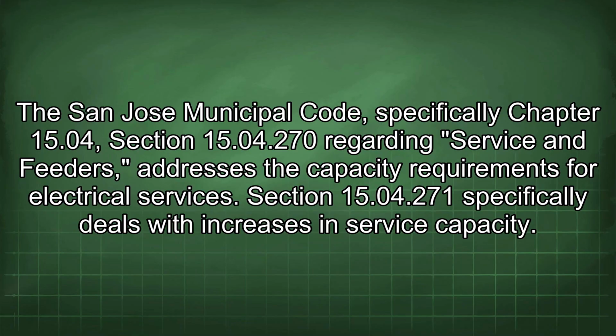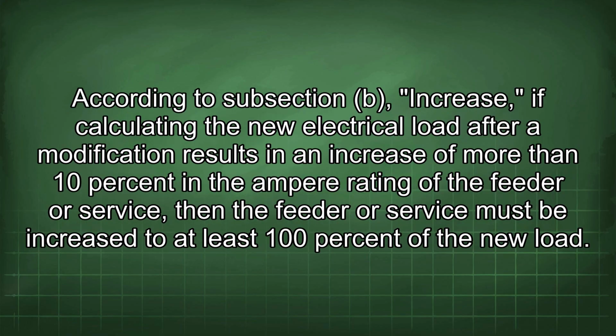The San Jose Municipal Code, specifically Chapter 15.4, Section 15.4.270 regarding service and feeders, addresses the capacity requirements for electrical services. Section 15.4.271 specifically deals with increases in service capacity. According to subsection B, increase, if calculating the new electrical load after a modification results in an increase of more than 10% in the ampere rating of the feeder or service, then the feeder or service must be increased to at least 100% of the new load.